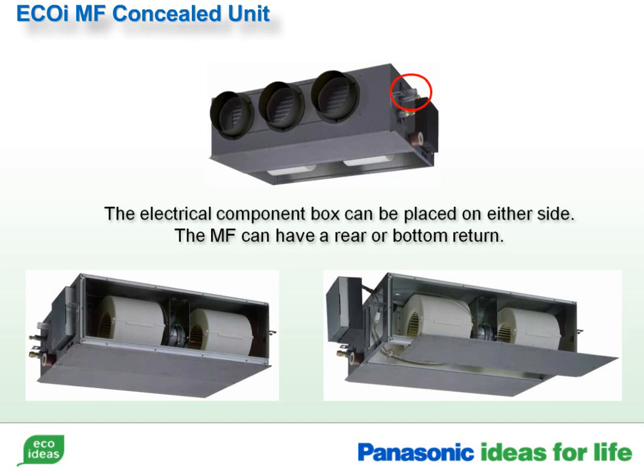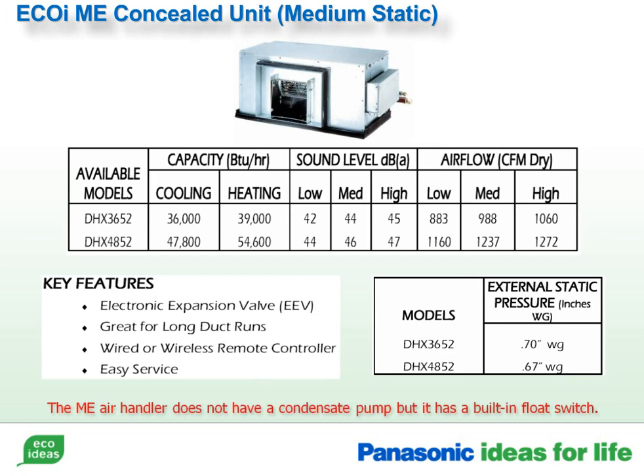The MF has a built-in condensate pump. The discharge is located near the top of the unit. The lower plug can be used to drain the unit of a coil cleaning solution. The ME concealed units have higher static pressure ratings. They also have no internal condensate pump, but there is a built-in float switch. This is the only model that requires a P-trap in the drain line. The filter and rack are field supplied.